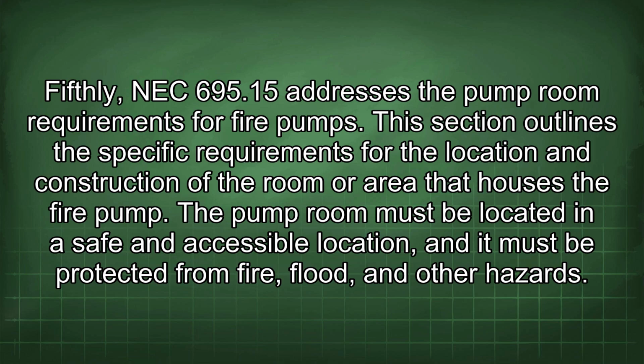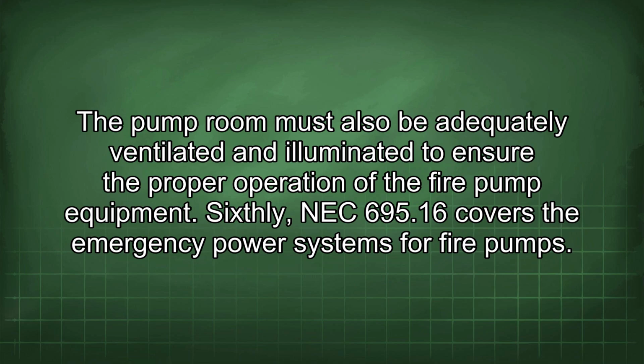695.15 addresses the pump room requirements for fire pumps. This section outlines the specific requirements for the location and construction of the room or area that houses the fire pump. The pump room must be located in a safe and accessible location, and it must be protected from fire, flood, and other hazards. The pump room must also be adequately ventilated and illuminated to ensure the proper operation of the fire pump equipment.